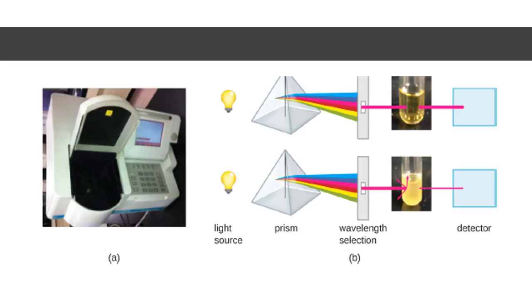The number of cells can be measured as a percentage of transmission, the percentage of the light that actually penetrated through the tube, or it could be recalculated using the logarithmic value of the amount of light that was absorbed by the cells that did not make it to the detector. So either way, we can represent this as a percent of transmission or as an absorbance value.